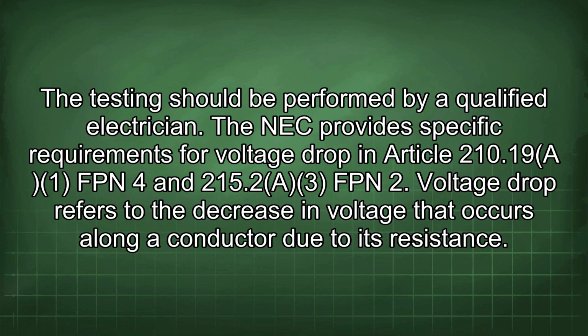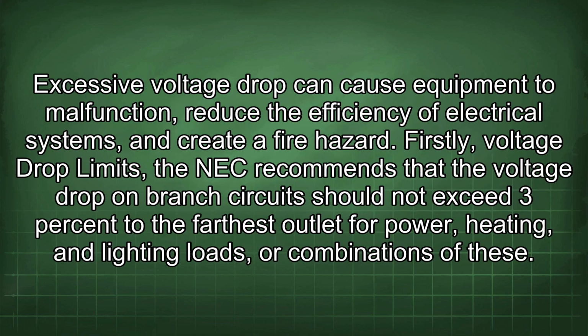The NEC provides specific requirements for voltage drop in Article 210.19(A) FPN 4 and 215.2(A)(1) FPN 2. Voltage drop refers to the decrease in voltage that occurs along a conductor due to its resistance. Excessive voltage drop can cause equipment to malfunction, reduce the efficiency of electrical systems, and create a fire hazard.